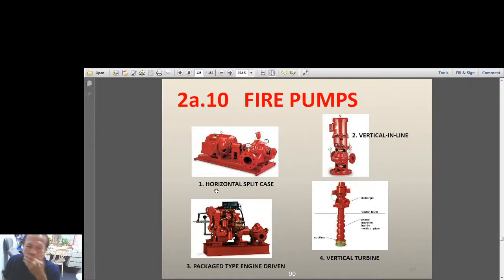Now we have these kinds of pumps. Horizontal split case. This is the most popular. Then here is a vertical inline pump. So the footprint is so small. You have here the intake and the discharge. Okay. So very small in space, while this one has a big base. Then here is the vertical turbine pump, for submersible use. So that means if you have an underground tank, you should use this vertical turbine pump to make sure that no cavitation will happen. Okay.